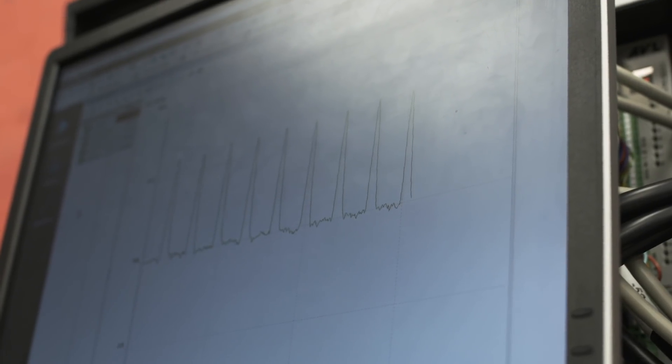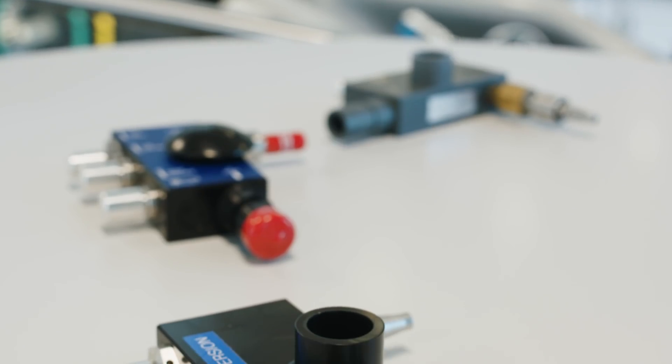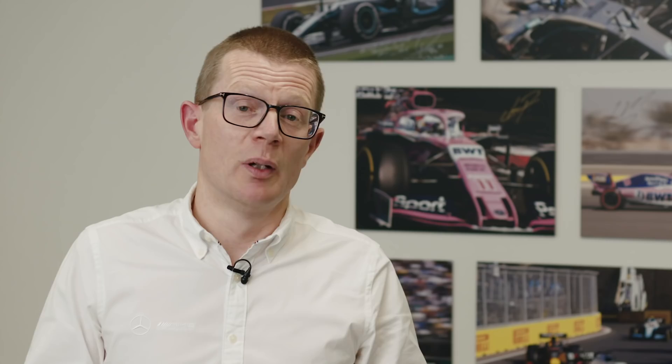With Mervyn Singer, we wanted to understand the breathing cycle — what is it like for people breathing in and out with COVID? That allowed us to create a breathing cycle for simulation and set up the test rig more precisely. We also worked with the government: initially the Cabinet Office, who funded the initial hundred we made, and then the Department of Health and Social Care, with three calls a week to discuss progress and distribution.